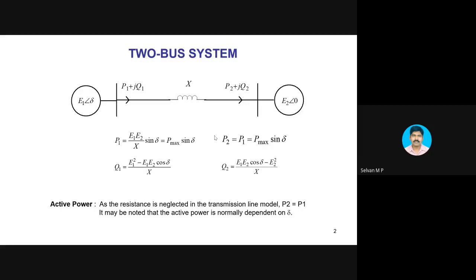So mostly under steady state condition, the angle delta will be maintained at 30 to 40 degree. If you have additional mechanisms to enhance the stability, of course we can increase this angle value up to 60-70 degree. Beyond that, it will be very difficult. But if you are capable of operating the delta near 90 degree, that is the best system where you are utilizing the capability of the complete transmission line. Here, when delta equals 30 degree, we are not utilizing the complete capability of the transmission line. Okay, this is with respect to real power. We will forget about that.